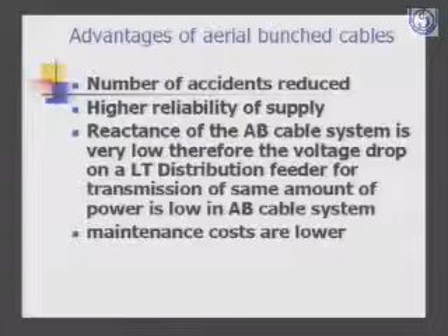Because underground cable is quite difficult to install. You have to dig the roads, and the cost is very high. But aerial bunched cables, the cost you can recover within 18 months or so. In 2 years or 18 months, especially in theft-prone areas, you get the returns very fast. And if this aerial bunched cable is used with a high voltage distribution system, what you say, sone pe suhaga, you get the returns very, very fast. Reduce both technical and commercial losses.